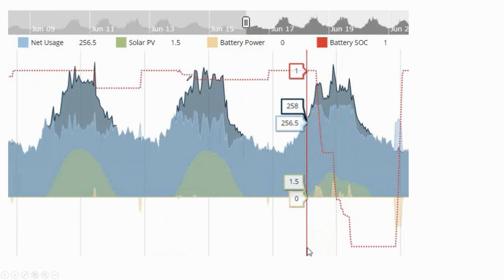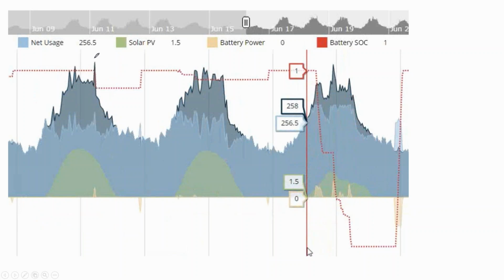What's interesting is the more demand you want to take off a facility, the wider the triangle gets, and the wider the triangle gets, the longer you have to run your battery during that time, which means you need a larger battery. Whereas if you're just trying to run your battery during a very limited window, you can run it, recharge it, and run it again, so you might just need a very small battery to substantially shave off that peak.